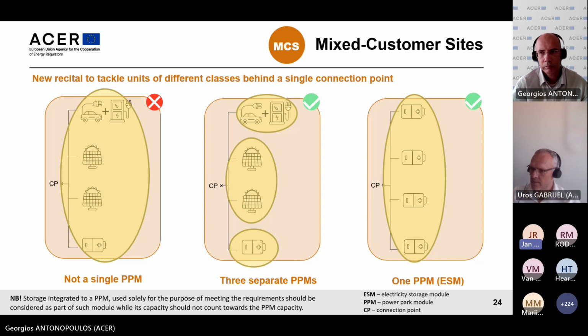No, it's not about defining the capacity. It's about the combined response from all units. If you have 50 megawatt of each, then all of them should be able to produce its own maximum, and that is the problem. It should be possible to define a limit so that I will never export more than the requirements.